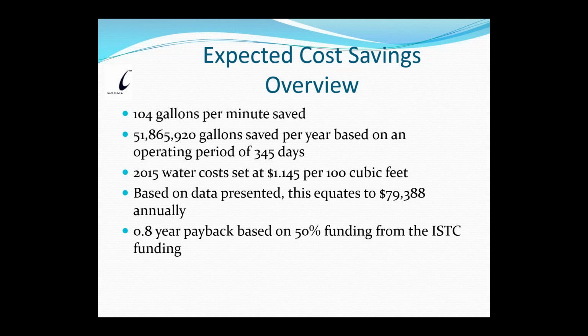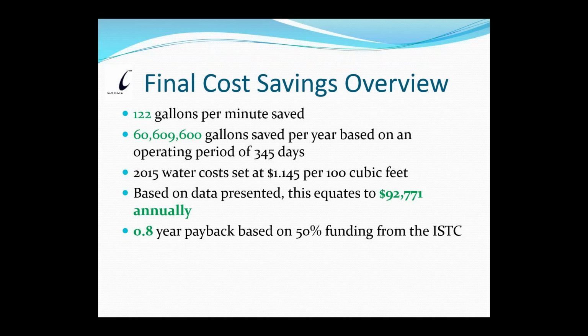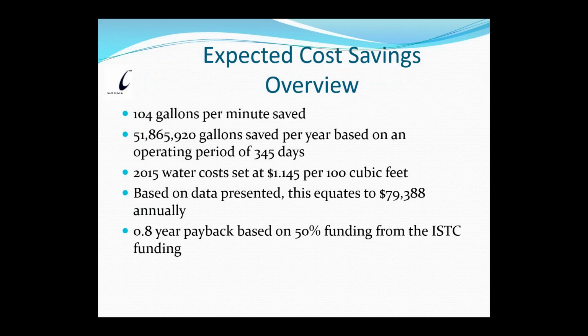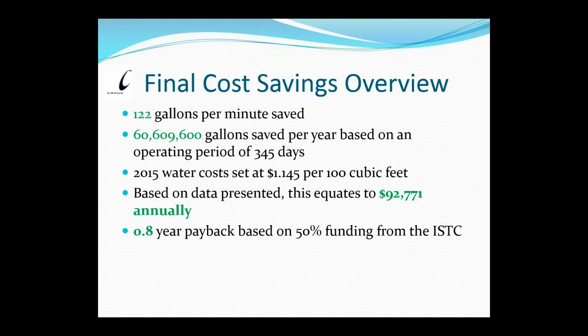So that's what I wasn't able to tell until we actually did the project and we weren't using city water anymore. I could then do the comparison, and the final cost savings overview wound up being 122 gallons a minute instead of 104. We're actually at almost 61 million gallons of water saved per year. And based on the water cost for 2015, that's an actual savings of $92,771 annually, with still a 0.8-year payback based on the 50% funding.